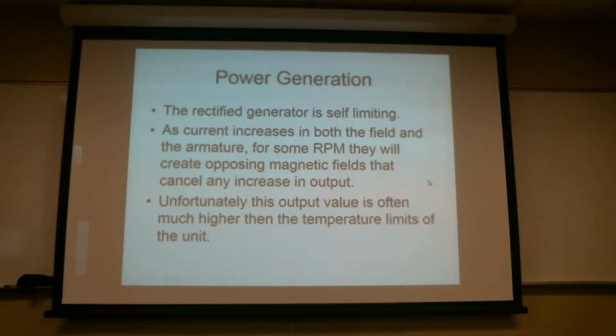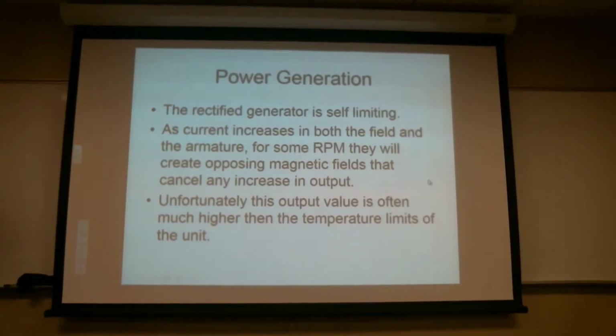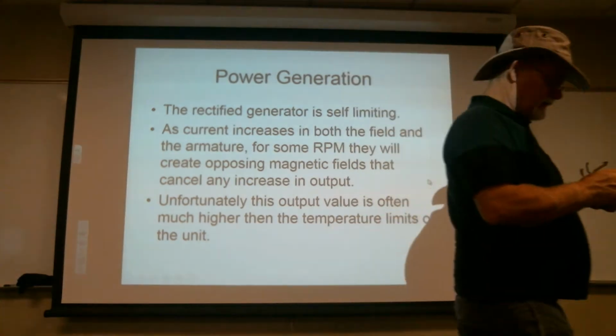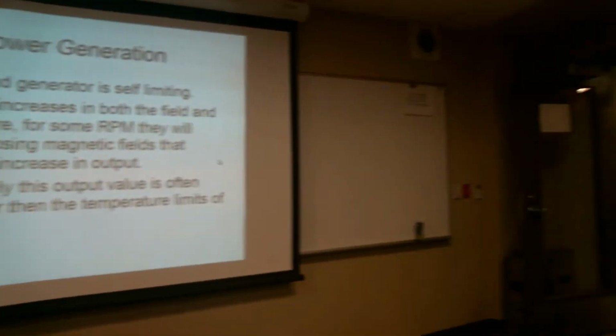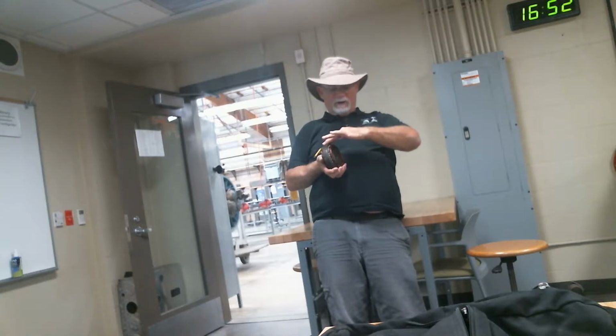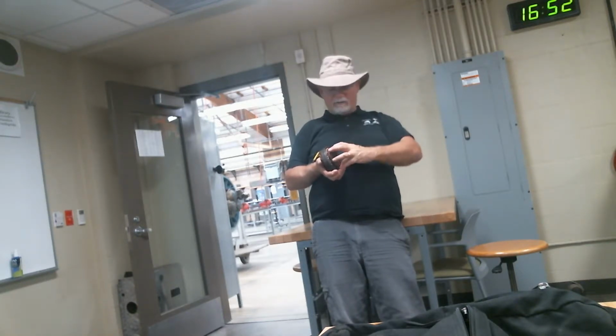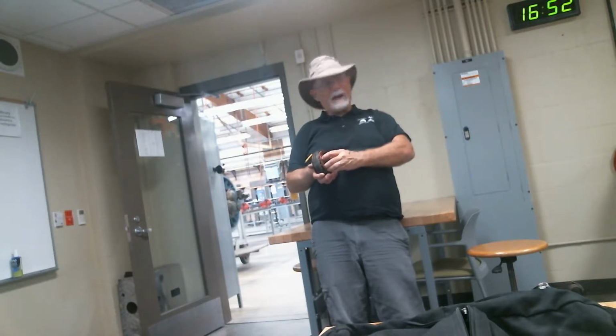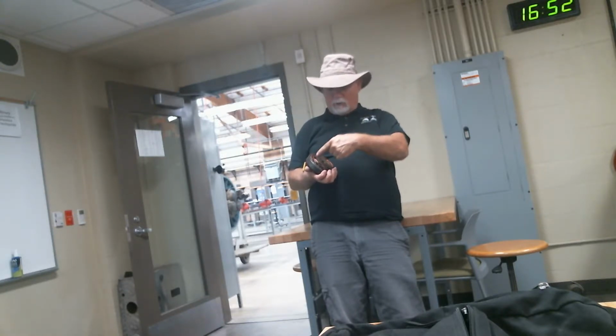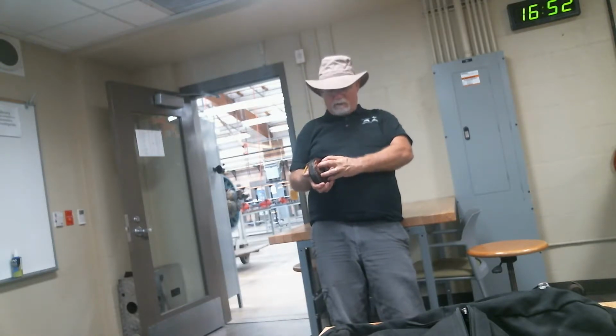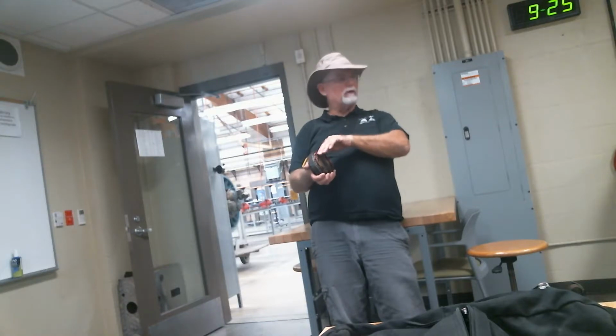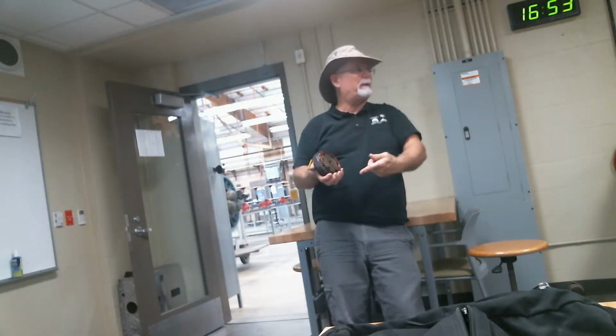It's true that the rectified generator, because we compress so much into such a small place, is self-limiting. There's a thing called armature reaction. In the commutator style generator, we had a field here and a field here, maybe one here and one here. As that thing spun around, there would be some dragging of the magnetic fields, but you could drag it quite a bit before they started impinging on each other. This one, where we're getting 12 north-south relationships all at the same time, I only have to drag it a little bit before the magnetic fields start distorting with the next pair in line.